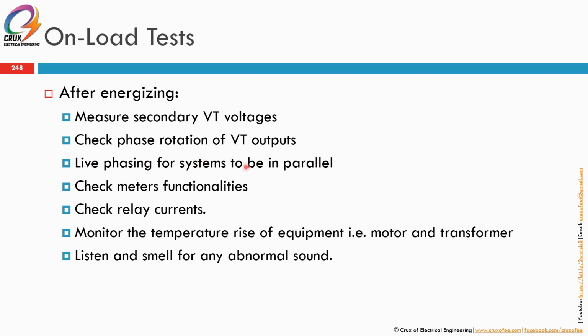These are for air insulated switchgear where you can still do live phasing. So for high voltage equipment where there's no facility for you to do live phasing, for example like 33 kV and above gas insulated switchgears, you don't have any points. You must make sure that there's another way of doing the live phasing, which we call a close on dead bus or blank phasing test, okay, but that is not explained here, so this is just the typical live phasing.